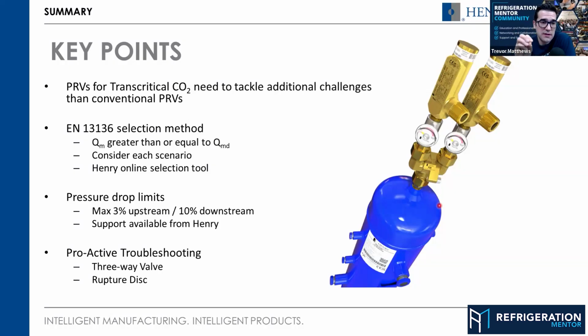I think those troubleshooting points are very, very important, because as technicians in the field, we don't see this a lot, especially if you're a service technician. We're going around doing the leak detection. Okay, we've seen it. It leaked, it ruptured, it had a pop off, whatever it is. Our job is to make sure the leak is done, because you always got to fix the leak, whether the pressure relief is a valve or a fitting that leaked. We got to fix that stuff and repair it, and then charge it back up. But diving a little bit deeper and understanding why you're doing this, I like the rupture disc, understanding what that is.